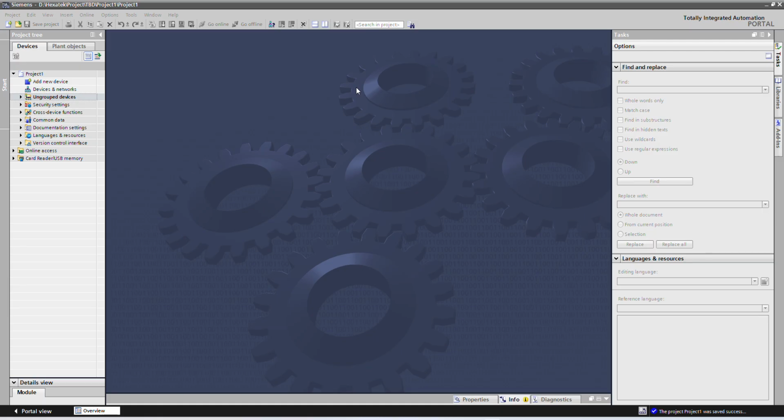Hello and welcome. In this video, we will see how to program analog unscale block in the TIA portal. In the automation system, we use analog signals to control VFDs, to operate control valves, or to give set points to the thyristors. To control these equipments, they don't understand engineering values, so we have to give them raw values. In Siemens it is 0 to 27648.